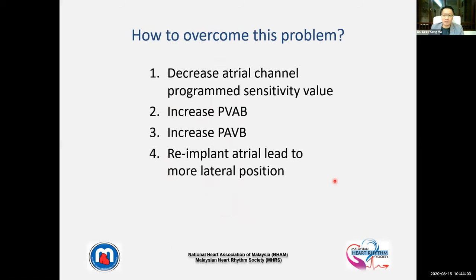How do we overcome this problem? In the interest of time, let's skip the poll. The answer is to increase the PVAB here, because you need to increase the atrial channel blanking period so it won't sense the signal happening in the opposite chamber. Now, why not decrease the atrial channel programmed sensitivity value? It's the opposite, you should increase the value. Increasing the value decreases the sensitivity. It's a bit counterintuitive here.